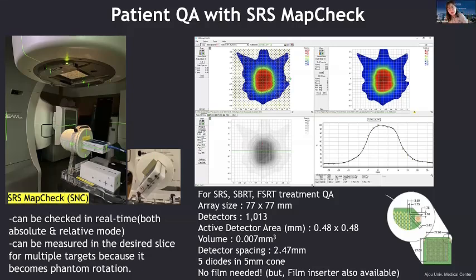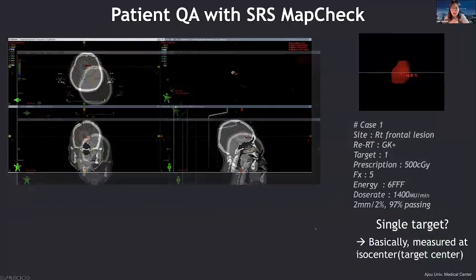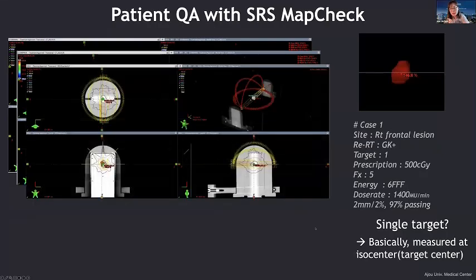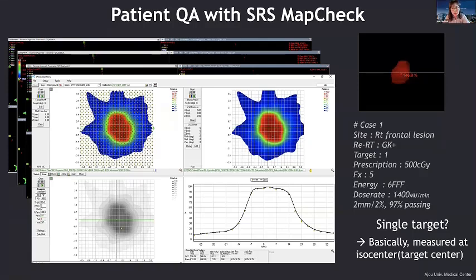So it can be measured in the most similar environment to the HyperArc, can be checked in real time, and can also be measured in a desired slice for multiple targets because it becomes a phantom rotation component. So this is a very straightforward process, with many ways to perform the HyperArc QA. In the case of single lesions, we usually measure at its isocenter and measure at non-coplanar angles like the HyperArc real treatments. Most single target cases passed at 99 to 100 percent without failure when we are doing the 2 mm/2% gamma evaluations.